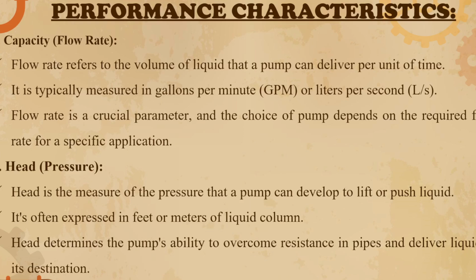Performance characteristics include capacity, just like with the other classification. It includes capacity or flow rate. For pumps, one characteristic is head or pressure head. It is the measure of the pressure that a pump can develop to lift or push liquid. It is often expressed in feet or meters of liquid column. Head determines the pump's ability to overcome resistance in pipes and deliver liquid to its destination.